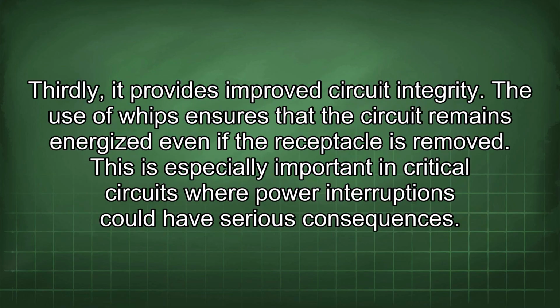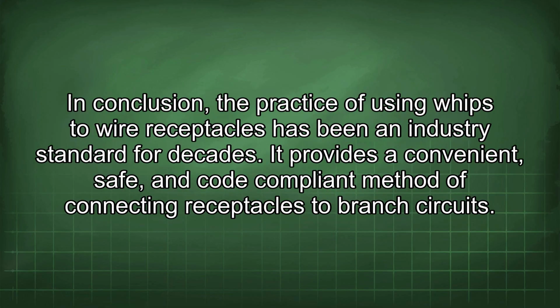Thirdly, it provides improved circuit integrity. The use of whips ensures that the circuit remains energized even if the receptacle is removed. This is especially important in critical circuits where power interruptions could have serious consequences. In conclusion, the practice of using whips to wire receptacles has been an industry standard for decades. It provides a convenient, safe, and code-compliant method of connecting receptacles to branch circuits.